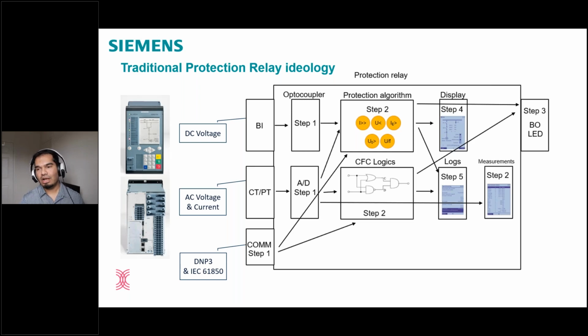And then you have different communication modules, as you can see at the bottom, COMM, that's communication modules, which will be responsible for horizontal communication between relays, for inter-relay communication, or vertical communication, which is responsible to talk to a control center or SCADA center. So all these external sources on the left-hand side, your binary inputs, your CTs, your PTs, your communication modules, all these external sources of information are then processed in the relay in the form of protection algorithms or CFC/PLC logic. So our PLC logics, we call them CFC logics.